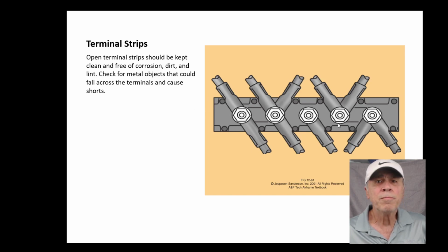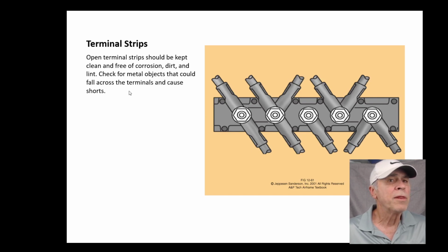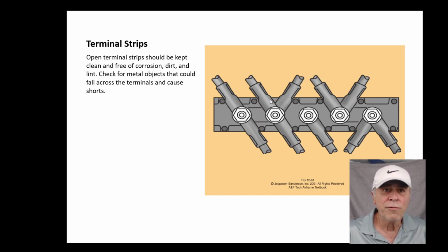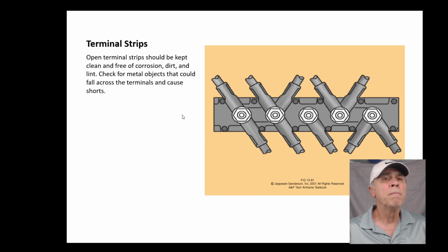Terminal strips. We don't have to talk much about that. Keep them clean and free of corrosion, dirt, and lint. Check for metal objects that could fall across the terminals and cause shorts. Some of them have guards so that they can't be turned. You certainly don't want to put more than 4 on one post. And there may be another rule that's escaping me at this point.